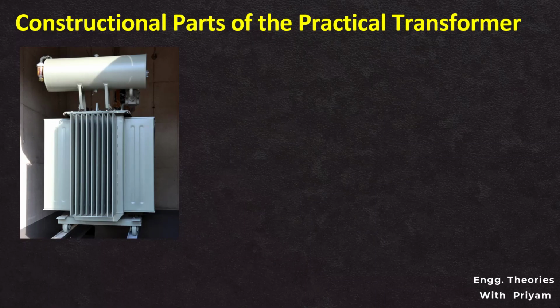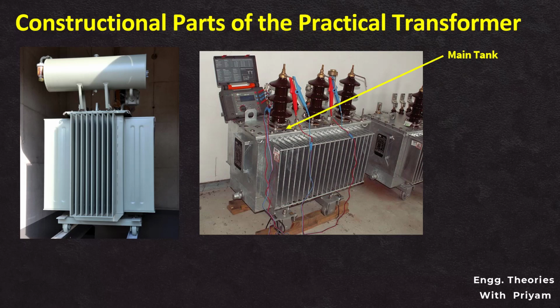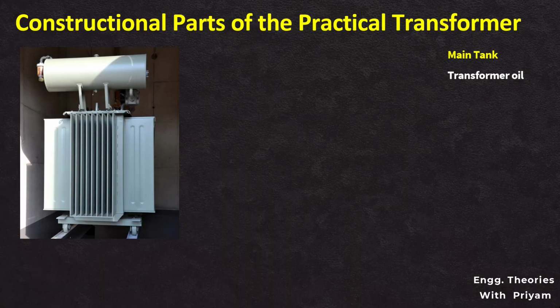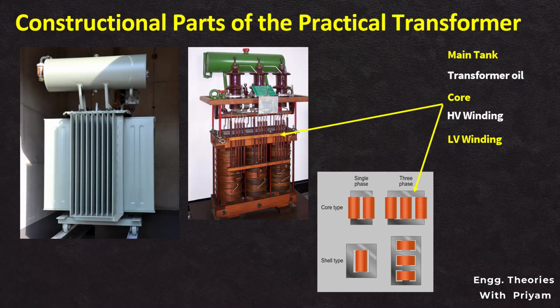First component is the main tank of the transformer. The transformer tank is the heart of the transformer setup. Its main job is to surround and protect the important inside parts like the core and the winding. The tank is especially made to hold the transformer oil, which is super important for keeping things insulated and cool. This setup helps to make sure the transformer works well and stays reliable by keeping the right temperature and insulation in check. Inside the transformer's main tank, transformer has a core and HV and LV windings.